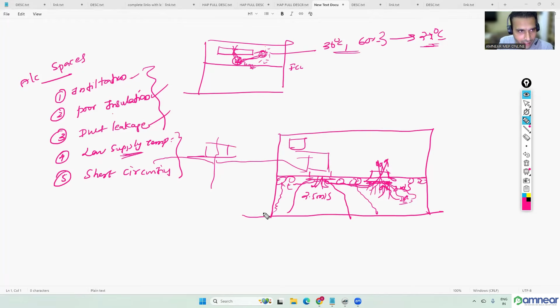In non-air conditioned spaces also it can come. In unconditioned spaces, this issue can come. Then the first reason might be contact with cold surfaces only. The second one, due to night cooling also this issue can come. Okay, for example, I'm having two spaces, and one space is an air conditioned space and the other one is a non-air conditioned space only. Let's say for example, it is open to atmosphere or whatever it may, just for class purpose. I'll be considering the temperature within the space is 36 degrees Celsius dry bulb temperature and 60% relative humidity. On that state, dew point temperature is 27 degrees Celsius.